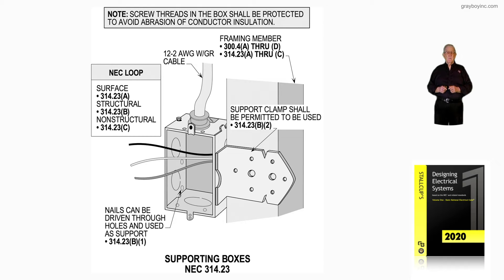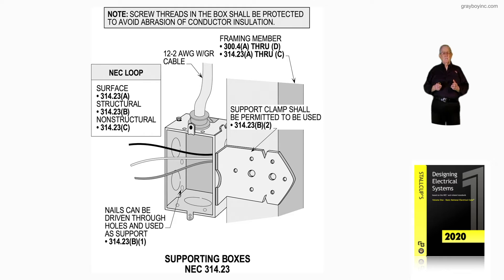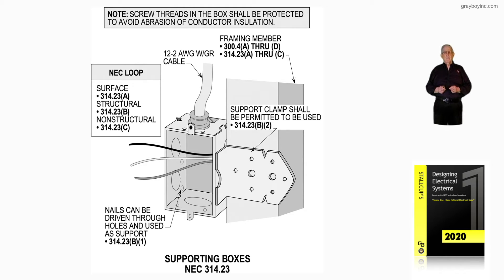Chapter 13 deals with supporting boxes, wiring methods, and so forth. This illustration illustrates supporting boxes in accordance with NEC 314.23. In the illustration we see a bracket that supports the box to the framing member. There are different ways of supporting these boxes — this is just one method shown using a support clamp designed for such use in accordance with 314.23(B)(2).